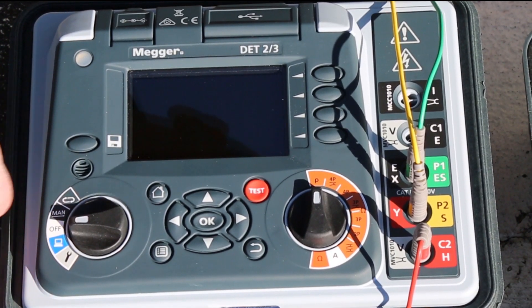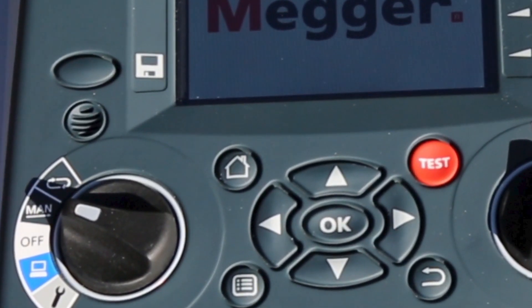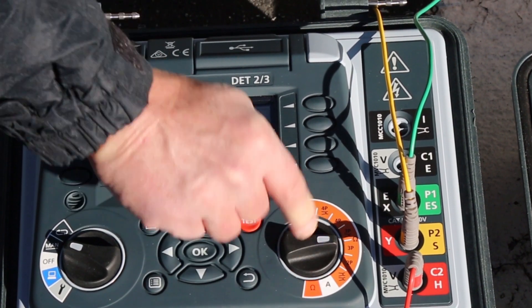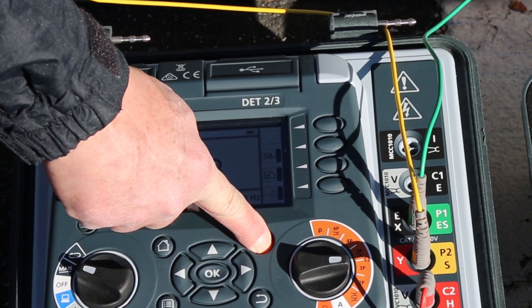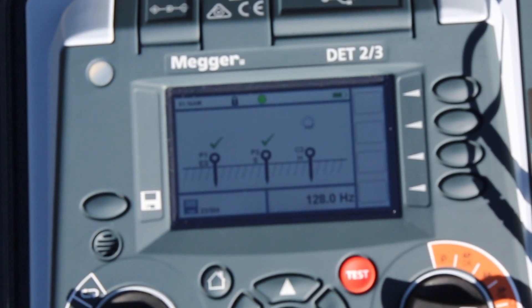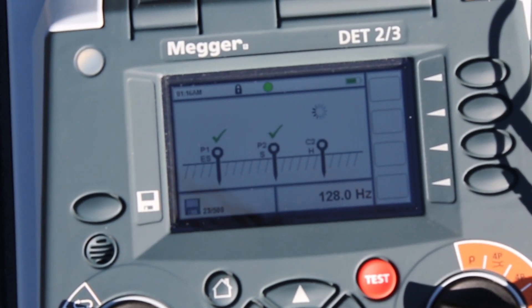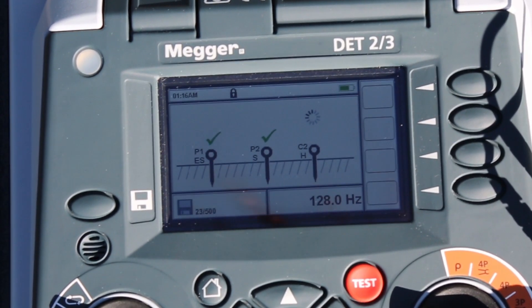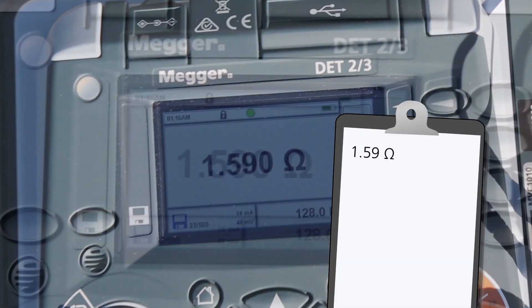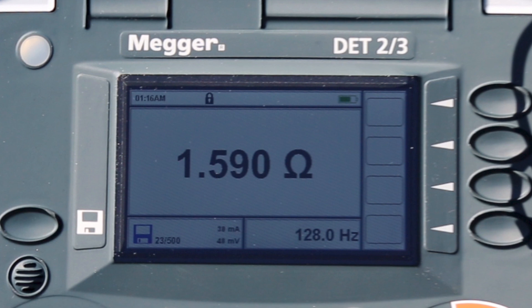We'll set the selector switch to the manual position. The continuous position helps in stabilizing readings in noisy environments, but here we're pretty quiet. Then we'll select a three-pole test. We press the test button and the display starts by indicating that the probes are making sufficient contact, indicated by a check. The current probe takes a bit longer because it must inject the maximum amount of current possible to get the reading to as many decimals as possible. Once accomplished, we see that we have 1.590 ohms. The test has been performed at 128 Hz, shown on the display, which is also adjustable to prevent noise interference.